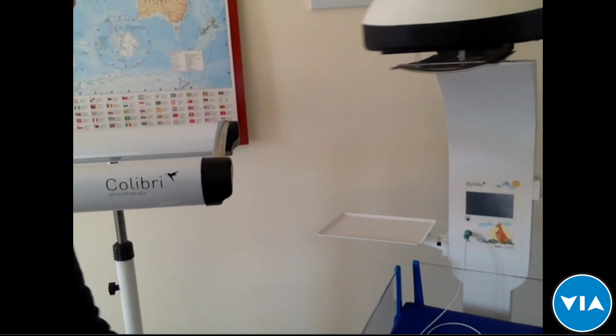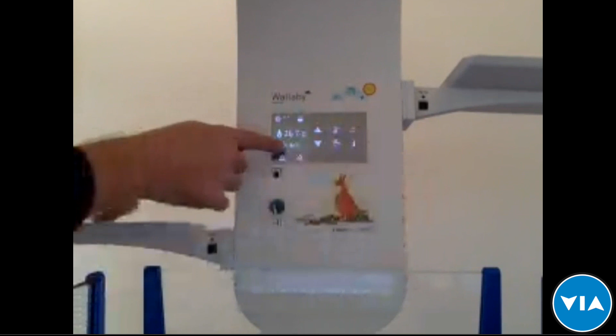Yes, the range is, in baby control mode, from 34 to 37.5 degrees Celsius. It starts as default from 36.5. Now I'll go to the minimum. This is the minimum, 34 degrees. Actual temperature that the sensor measures is 27.1 now. And now we can go to maximum, 37.5.